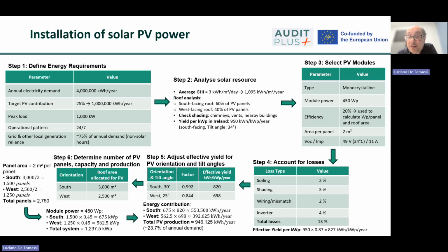Once the resource is understood, PV module selection is made based on efficiency, physical size, degradation rate, temperature coefficient, cost, and compatibility with site constraints. Higher efficiency modules are preferred where roof space is limited, while standard efficiency modules may be used where space is abundant. Module type also influences system voltage, string design, and inverter selection. System losses are then accounted for to convert theoretical generation into realistic output. These losses include soiling losses from dust on panels, shading losses from partial obstruction, electrical mismatch losses between modules operating under different conditions, DC cable losses due to resistance in wiring, and inverter conversion losses when DC electricity is converted to AC.